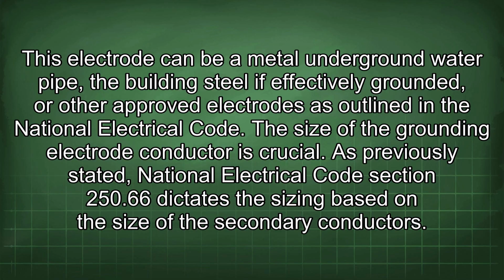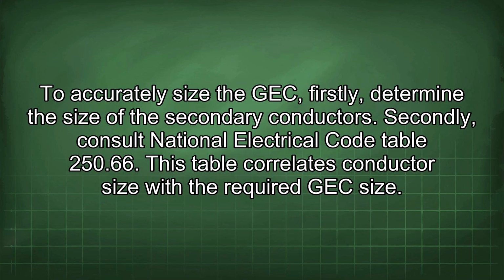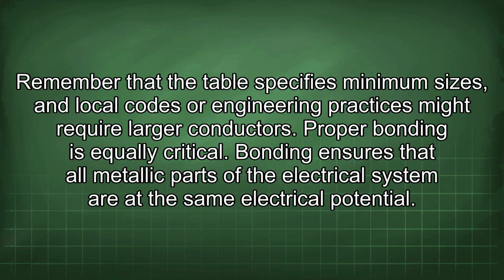The size of the grounding electrode conductor is crucial. As previously stated, National Electrical Code Section 250.66 dictates the sizing based on the size of the secondary conductors. To accurately size the GEC, firstly, determine the size of the secondary conductors. Secondly, consult National Electrical Code Table 250.66. This table correlates conductor size with the required GEC size. Remember that the table specifies minimum sizes, and local codes or engineering practices might require larger conductors.